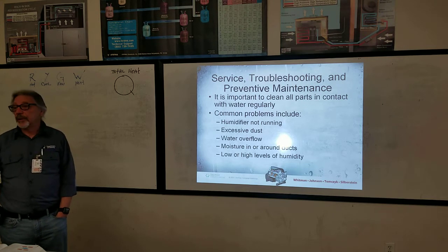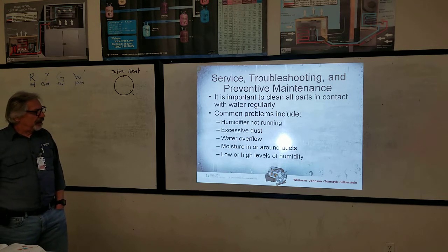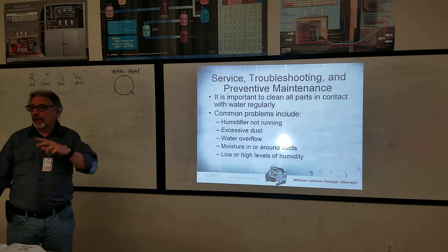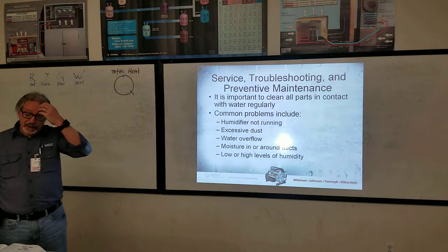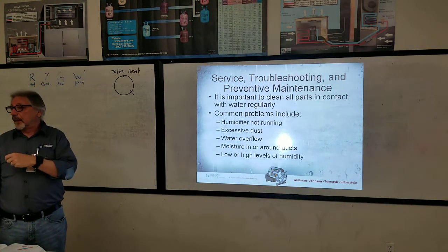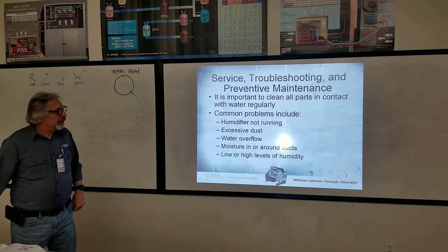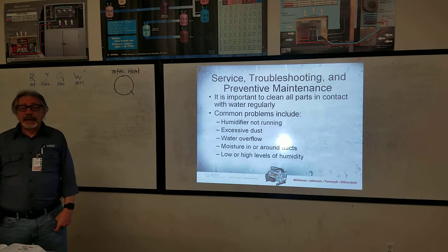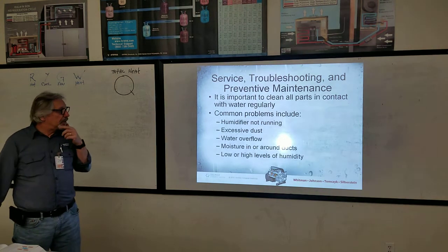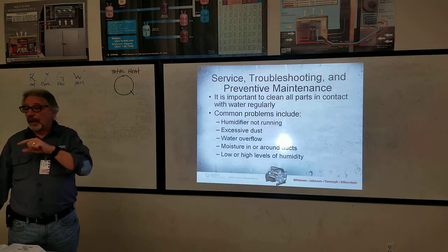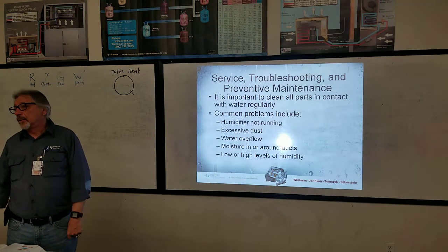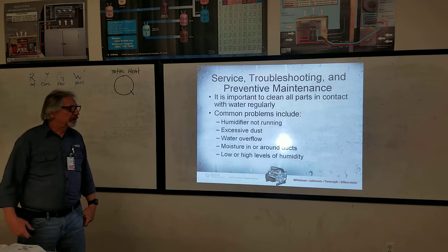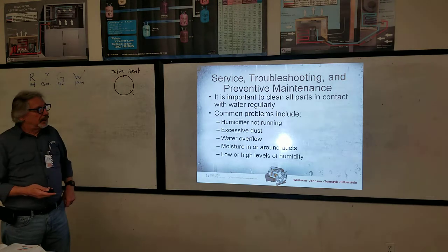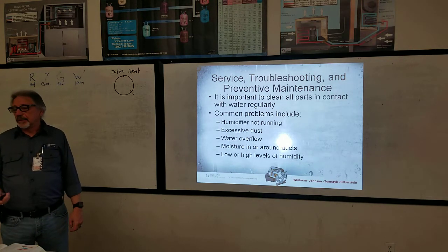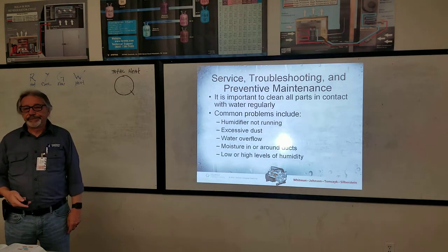Another time I was out there, the humidity was too high or too low, I forget which. I took the humidifier apart, cleaned it all up, and set it back online, but we still were getting alarms about the humidity being too low. So I went back out there and went through it again, and couldn't find anything wrong with it. So I actually got into the thermostat and adjusted the parameters to have a wider range, so the alarm wouldn't go off as much, since I got tired of going out there fixing the thing. And humidity in a server room isn't really necessary, but you just want to cool it.